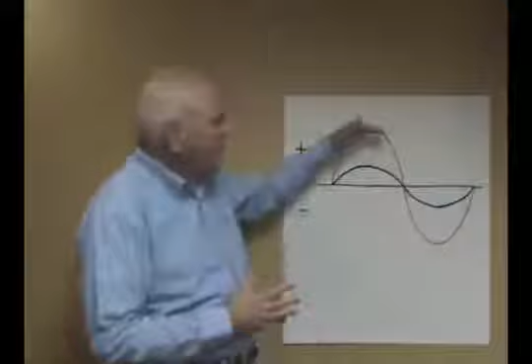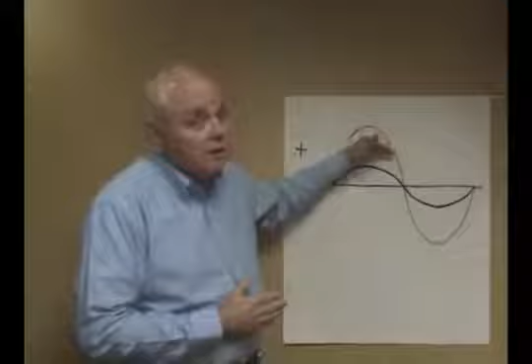Are my voltages balanced from phase to phase? If not, I can destroy motors. Are the magnitudes of my voltages too high or too low? Often if they're too low, I can end up burning up equipment. In other words, do I have what we call swells and sags on our voltage levels?